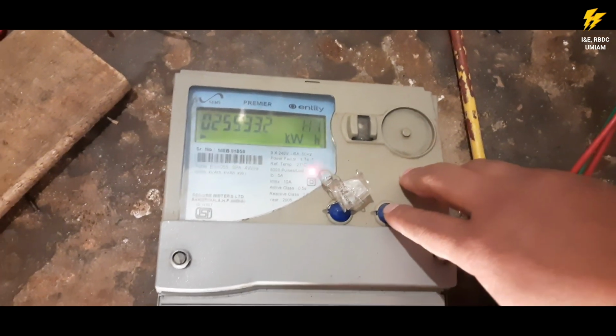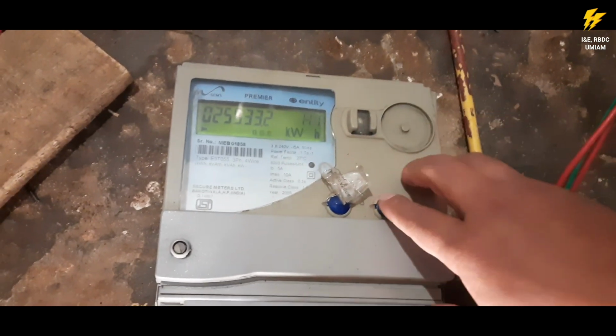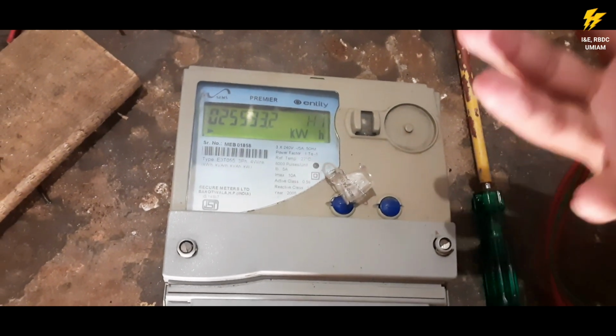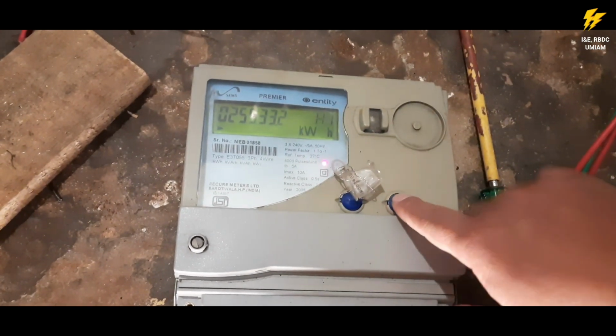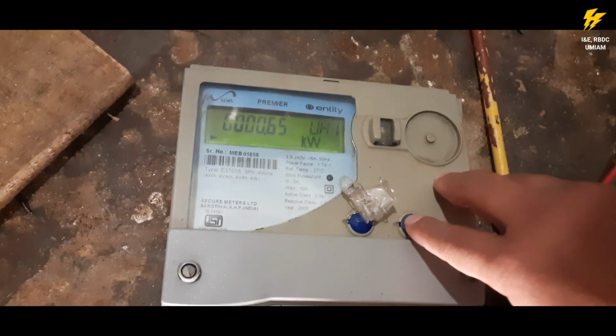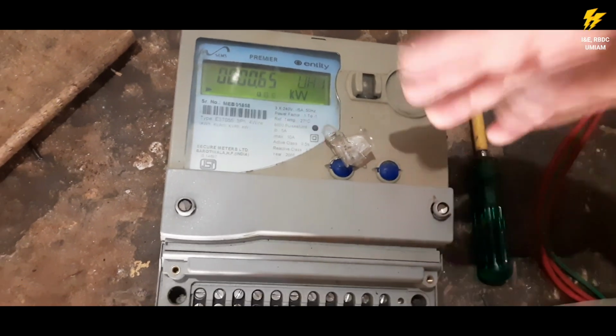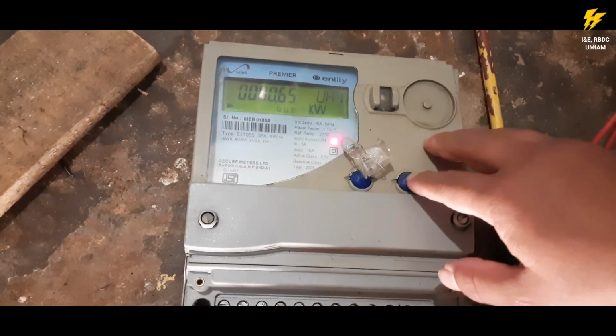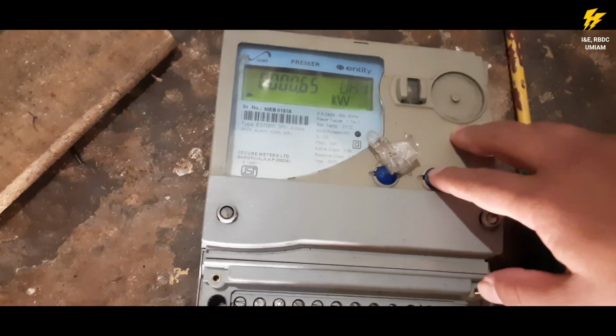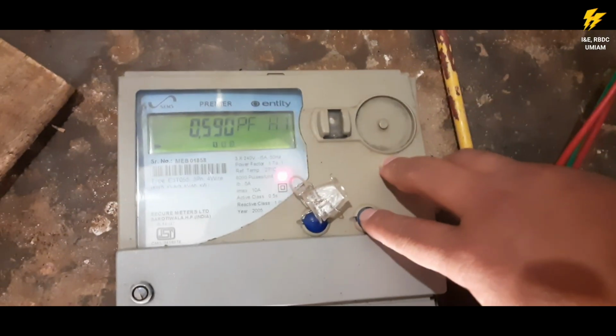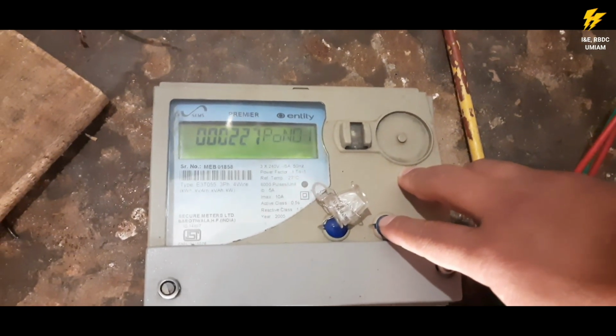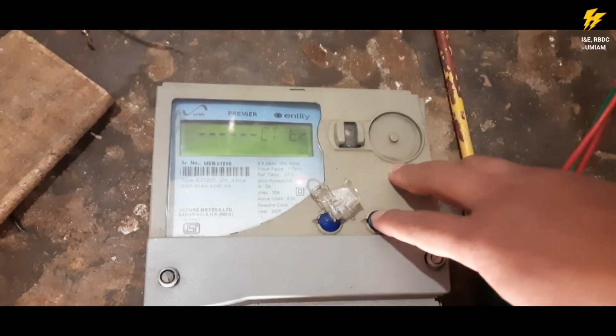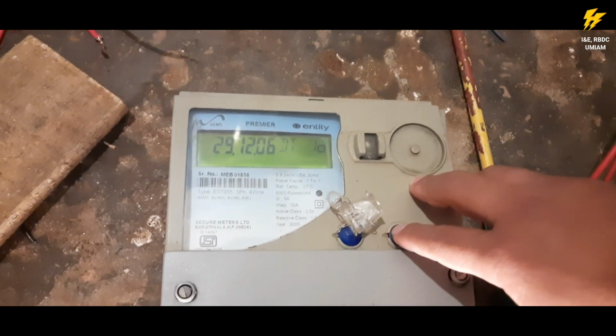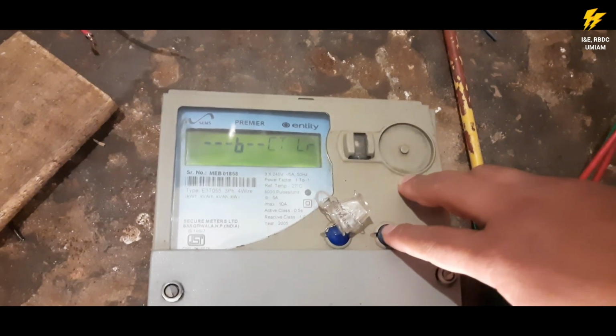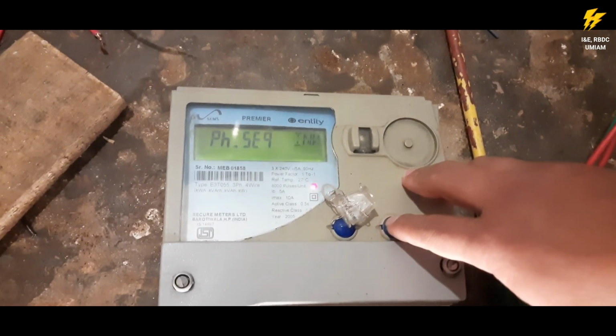All right, now kWh, this is H1. For example, now it is October, so this is of September, this much. And then the maximum demand of September was 0.65 kW, and the power factor is 0.59. It has been on for 227 hours, so like this. Okay, so this is how you take the reading of this meter. It's quite easy.